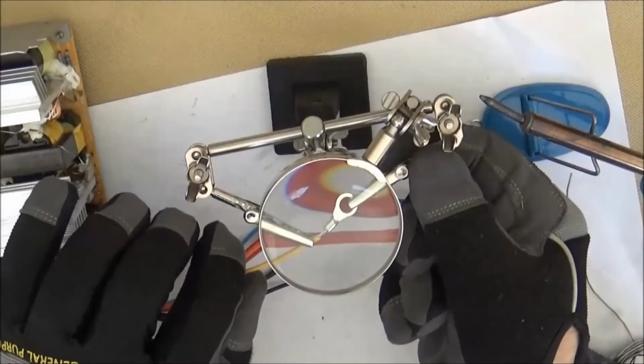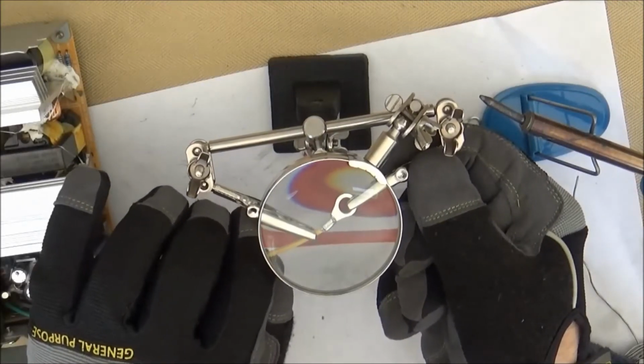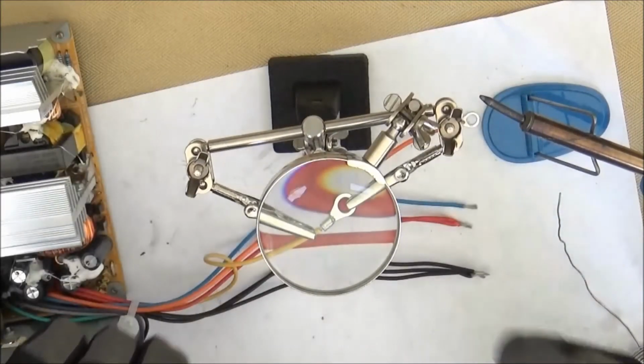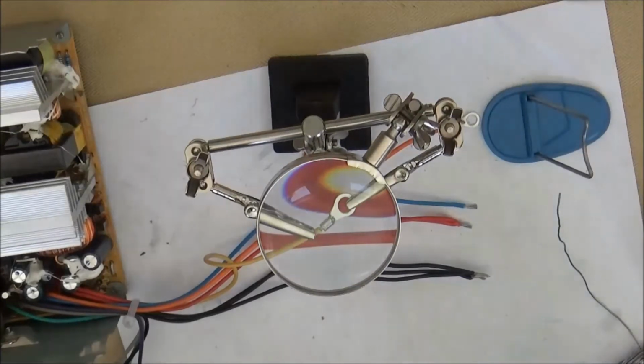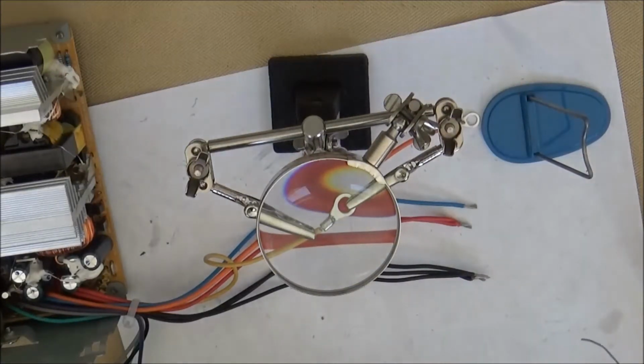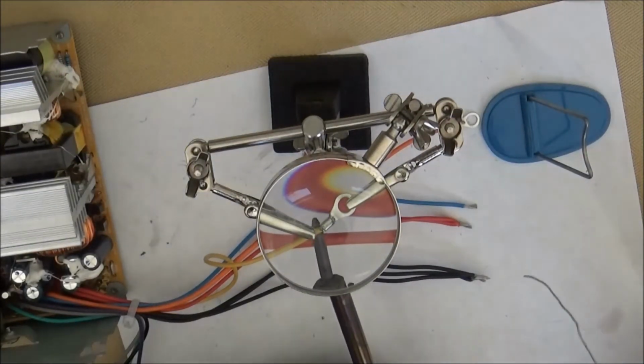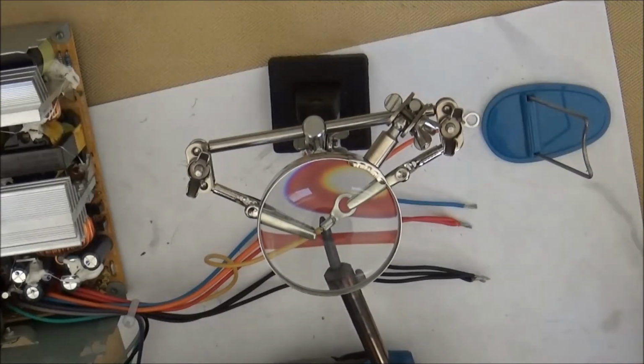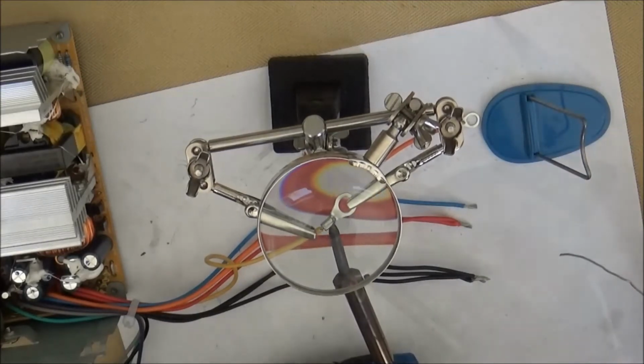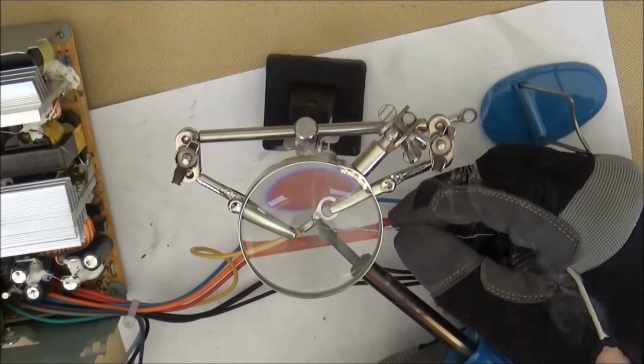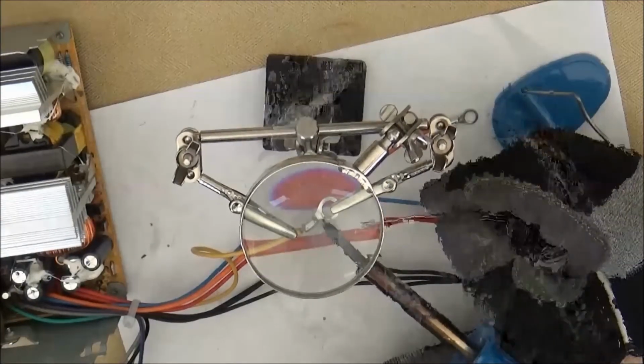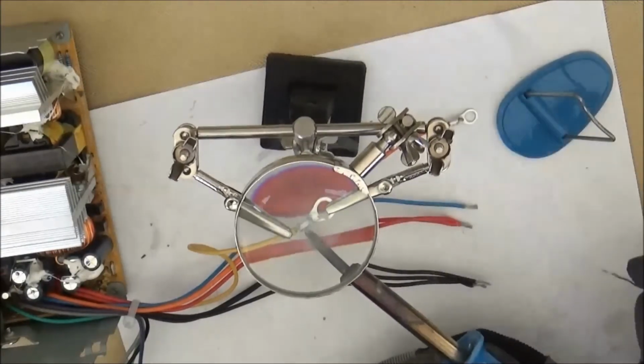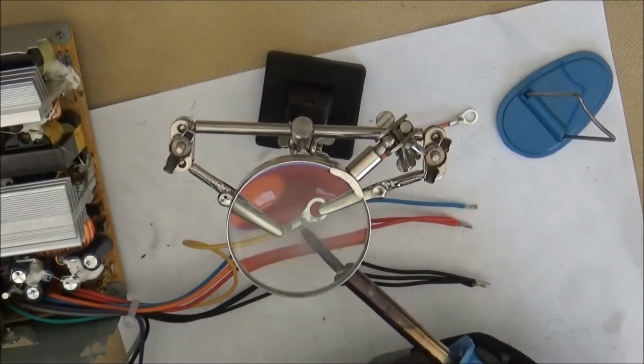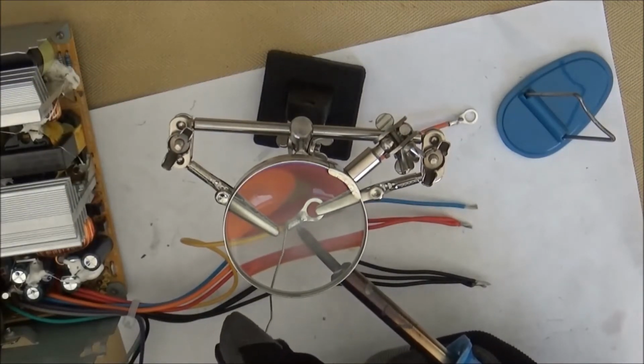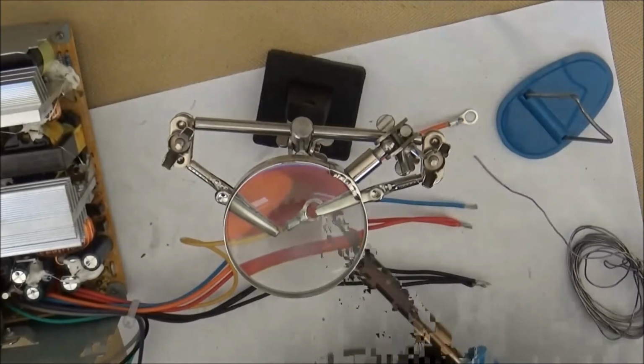Here you can see I've stripped back the coating on the wire, and I'm going to solder on a connection. You do not have to solder on connections. You can use crimp connections for this. As you can tell, it would have been impossible to use a crimp connection if we had left all 7 yellow conductors on the power supply. When making your solder joint, it's important to make sure the barrel is filled and you've got good flow on the wire and the connector.